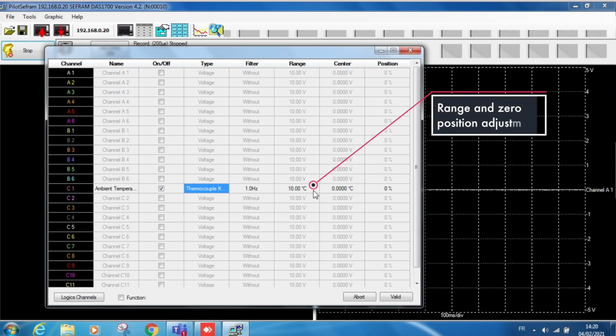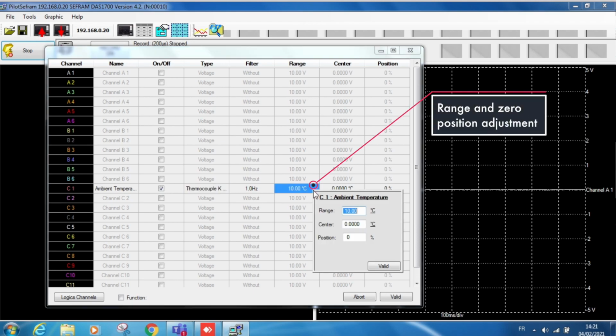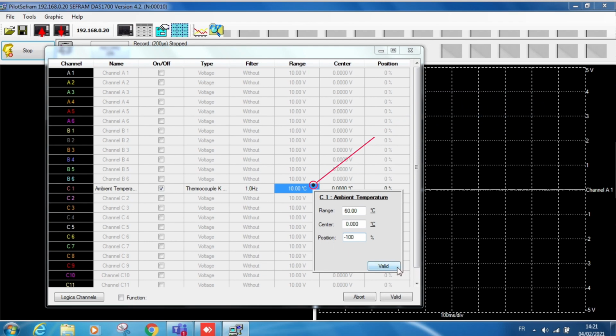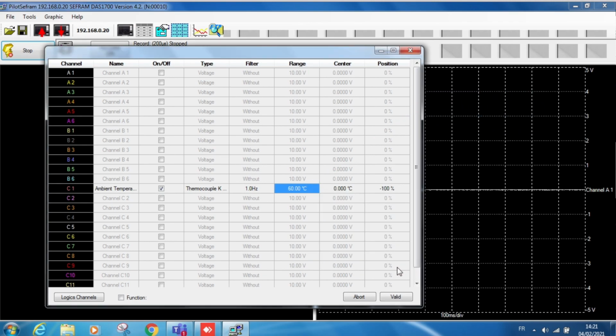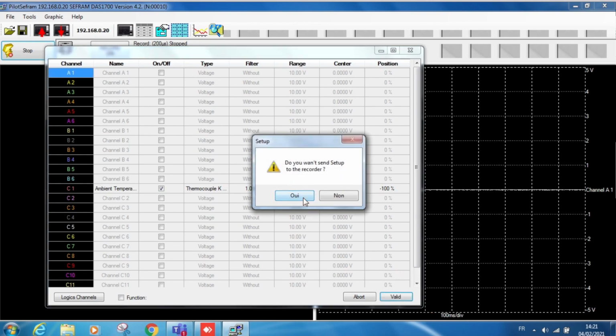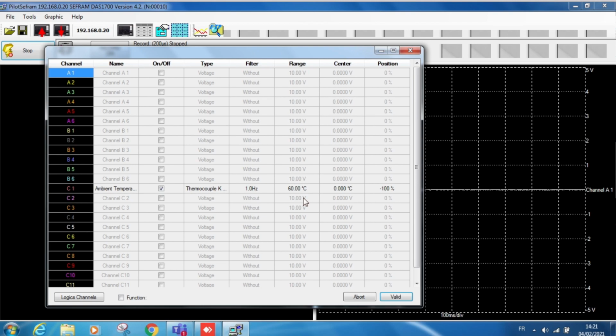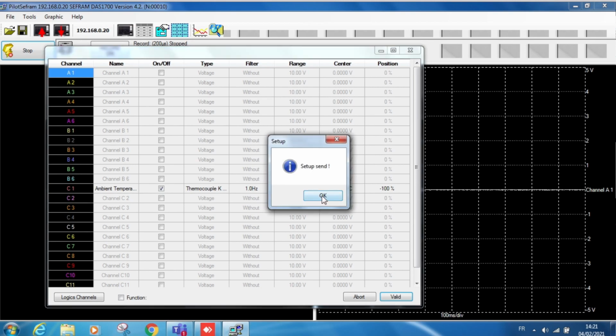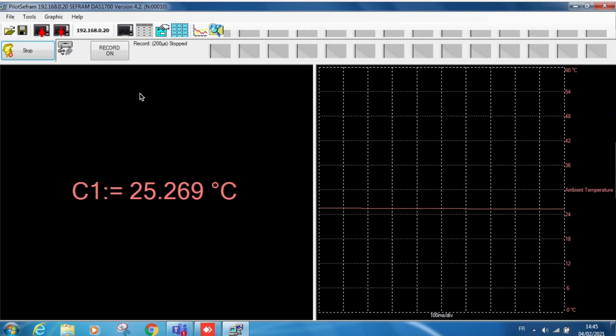Let's define our range by putting a 60 degrees range with a position from 0 to -100% to have a range of display from 0 degrees to 60 degrees. Validate and send this configuration to the device. The device is well configured. We can visualize our signal and we can see it change.